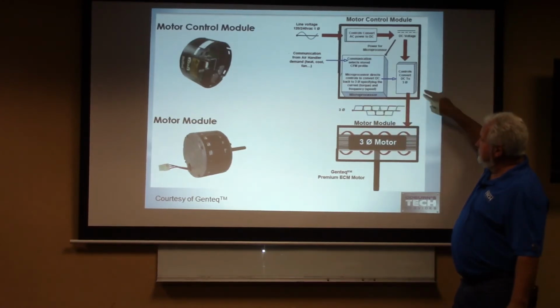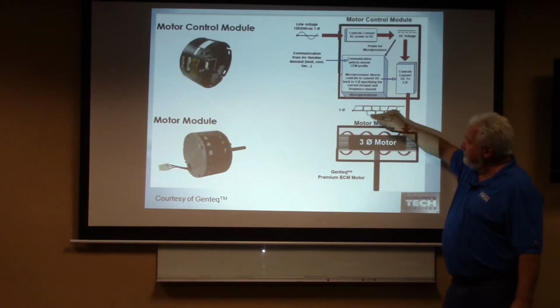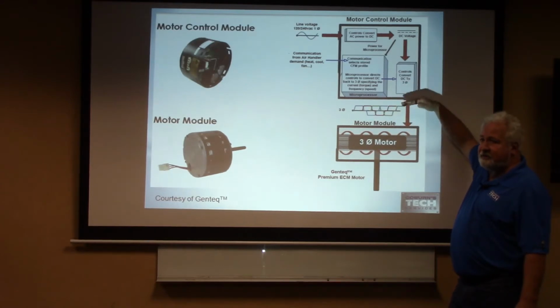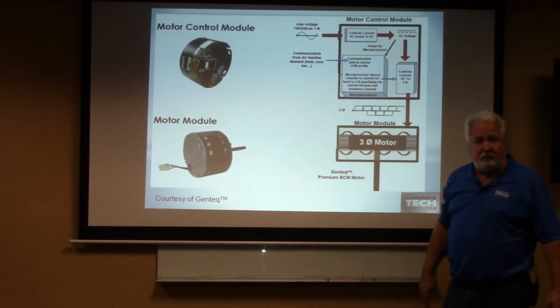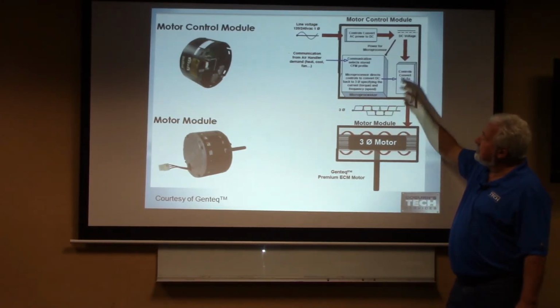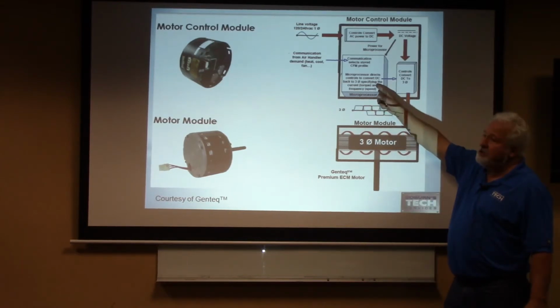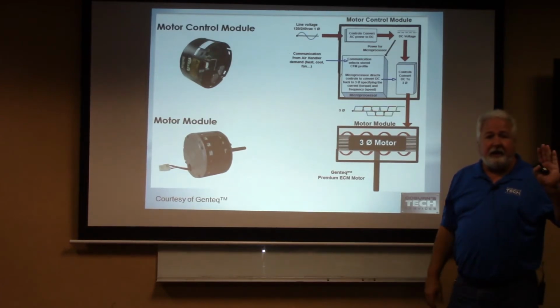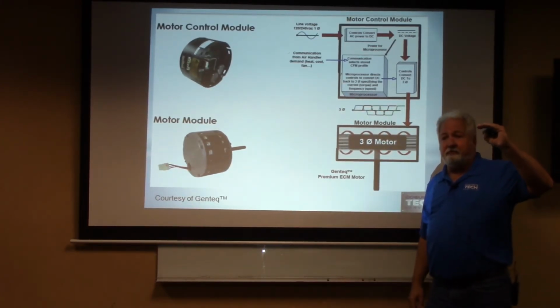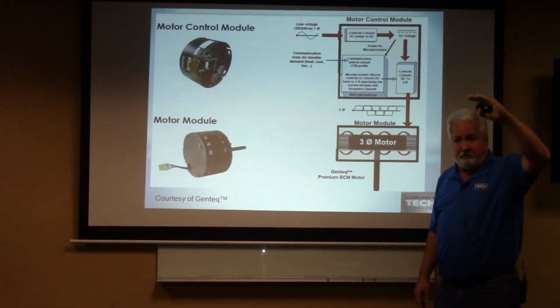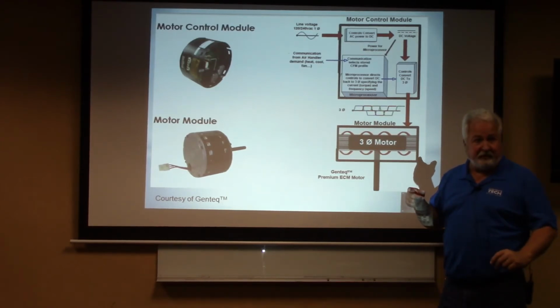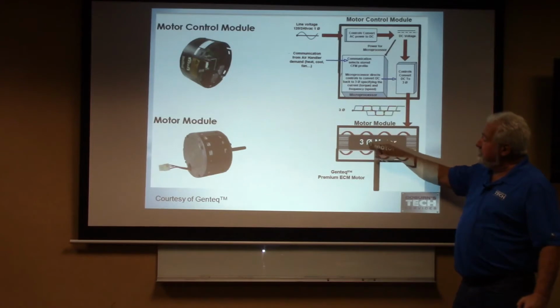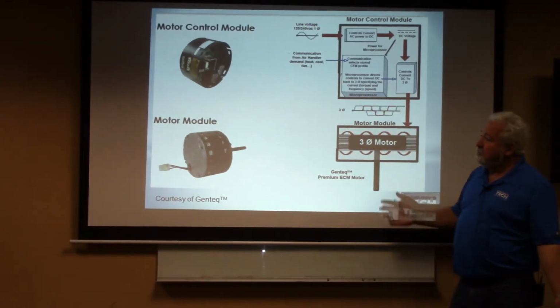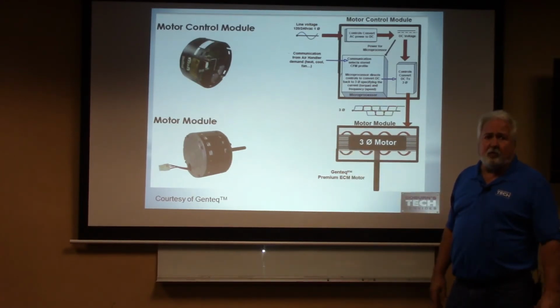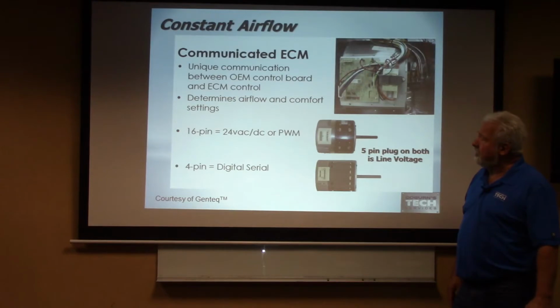So instead of it doing a sine wave, it's DC. It's on, off, and it just changes that sine wave to a direct current, but it's a pulsating DC current. So we're going to change that AC current into a three-phase pulsating DC current. The communication part of this is going to say, I need that voltage to be 3 volts, 5 volts, 7 volts, whatever it is. The higher the voltage, the faster it's going to spin. Does that make sense? Good. So coming back out of it, you end up with a 3-phase motor at the other end. Knowing that I have a 3-phase motor, I know that the windings should all have basically the same resistance. Does that make sense? Good. So it's going to be easy for us to check this out.